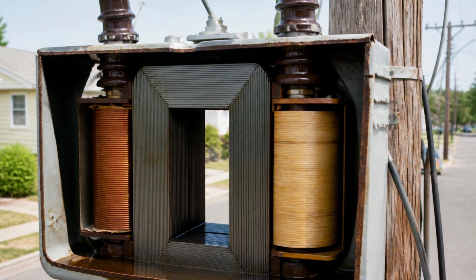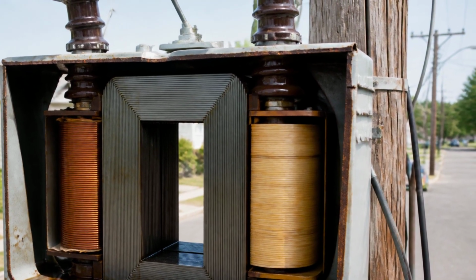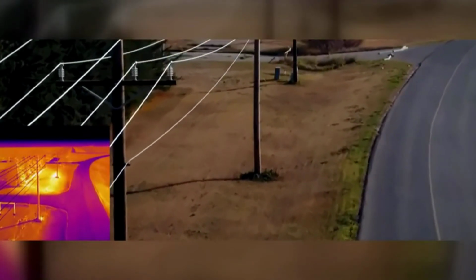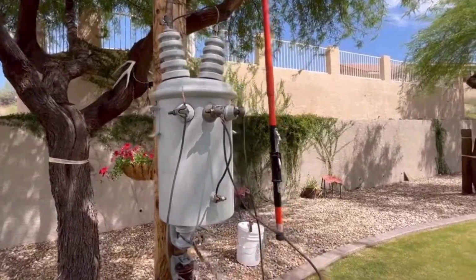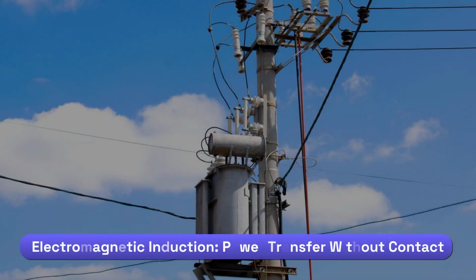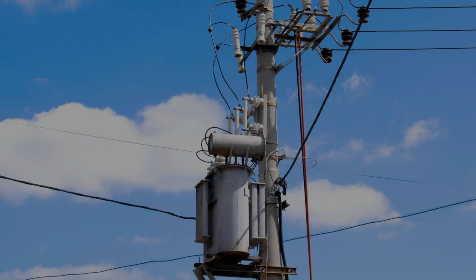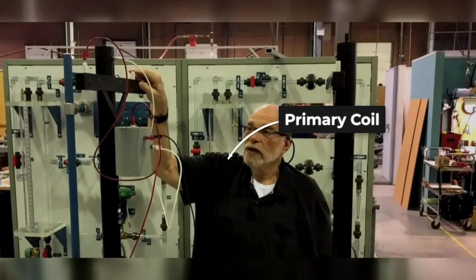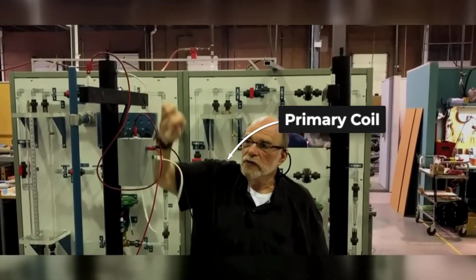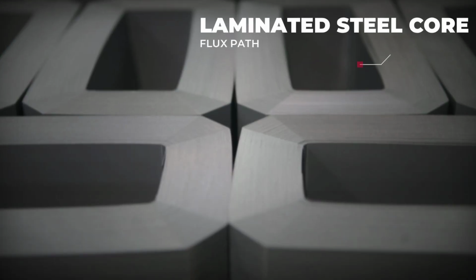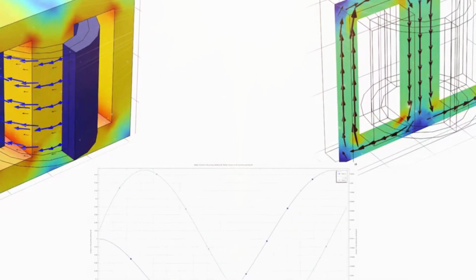Inside the tank, these two sets of coils never actually touch. There is no physical wire connecting the high-voltage utility grid to the low-voltage lines feeding into a home. Instead, the transfer of power relies entirely on electromagnetic induction. When alternating current from the distribution line flows into the primary coil, it generates a constantly expanding and collapsing magnetic field. The laminated steel core channels this moving magnetic flux, guiding it directly through the secondary coil.